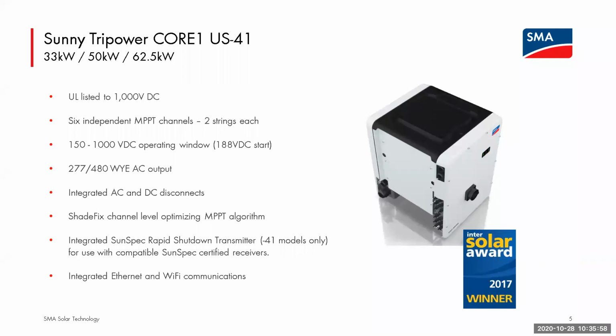Building on the Sunny Boy, when you move into the commercial solar install space, the Sunny Tri-Power Core 1 has been just a blockbuster inverter over the past few years. It's the #1 selling commercial inverter in the US over the past year. This is a 1,000-volt DC rated inverter. So instead of 3 MPPTs like the Sunny Boy, the Core 1 has 6 independent MPPT channels with 2 string inputs per channel. So up to 12 strings can plug directly into this inverter.